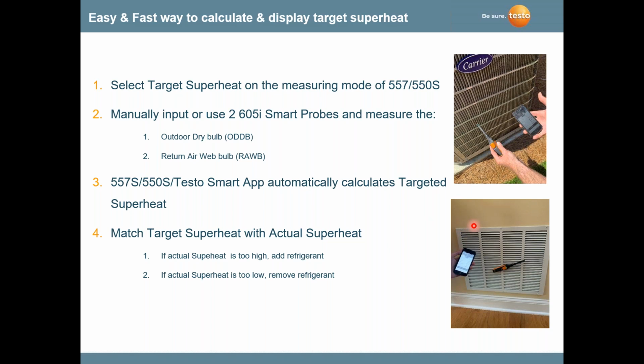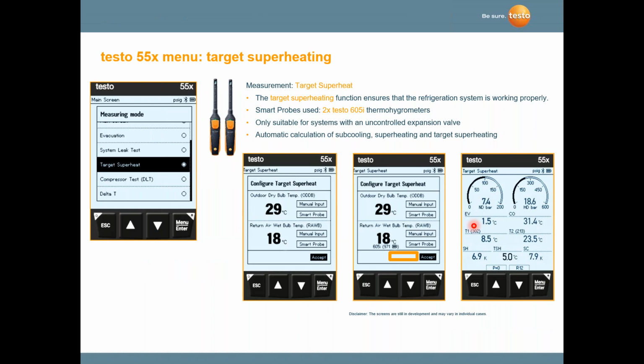You'd need to figure out the targeted superheat. With today's instruments, by using two of the digital gauges, which are Bluetooth right into the gauge, and I apologize to the United States here, but this is in degrees Celsius instead of Fahrenheit, but it would read degrees Fahrenheit in the States and degrees Celsius in Canada. These would input the data to get your targeted superheat, and your instrument would read your pressures, your temperatures, your line temperatures, your targeted superheat, and your actual superheat automatically. So it's giving you a quicker, faster, more accurate reading, and also a real-time measurement.